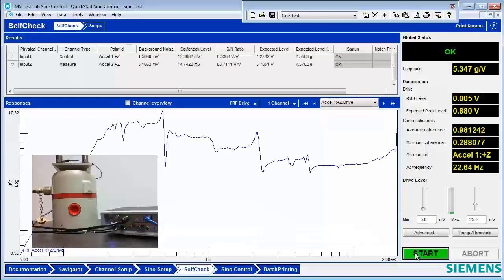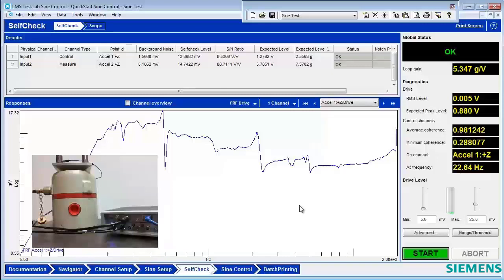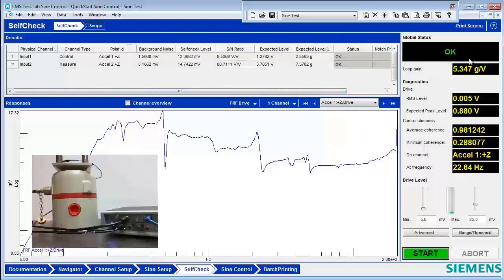And now we have a successful self-check. We can see we have a nice transfer function between the control accelerometer and the drive. The channel statuses are all okay, and the global status is all okay. Hope you enjoyed this video about self-check.